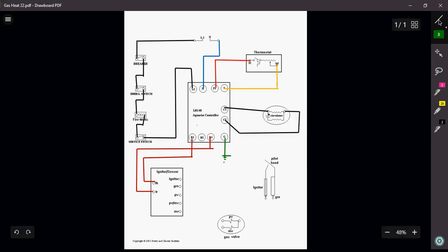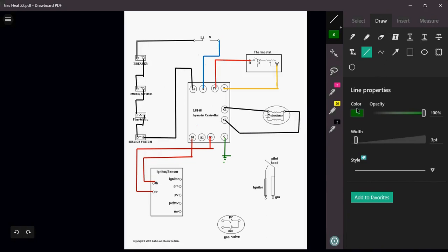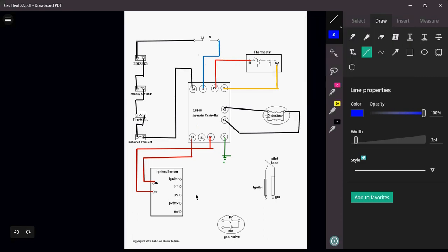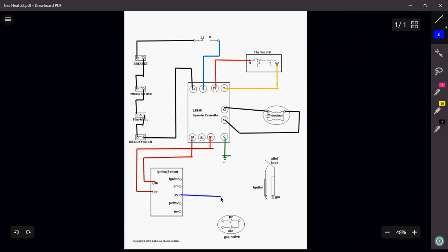After all of that is said and done, I can now simply focus on my igniter and my gas valve. That is all relatively cut and dry, especially if we already know how to wire a gas valve and an igniter. It's basically just plug and play. So we go to PV, and we can go to MV, right? Because remember, PV is my pilot valve, MV is my main valve, and PV-MV is my common.